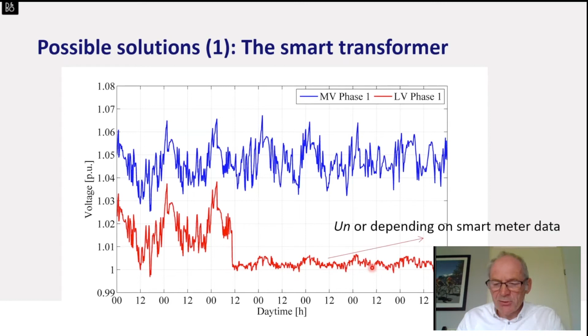Another possible solution is the curtailment of active power. So the moment you reach the limit of voltage in the low voltage network, you could limit the PV power produced at a certain level. It could be 70%, could be 60%, depending on the voltage.